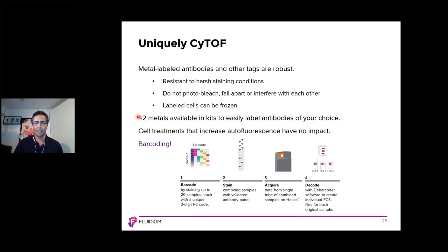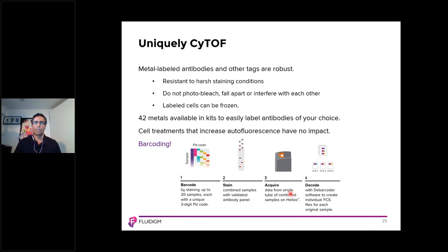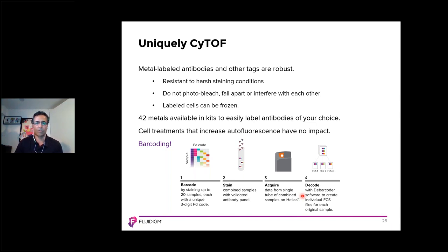Labeled cells can also be frozen and stored at minus 80°C with little to no impact on staining quality. Fluidigm also offers 42 metals available in kits to easily label antibodies of your choice. Finally, there is the barcoding option. Mass cytometry is the only high-parameter cytometry platform which enables barcoding. Fluidigm's barcoding kit allows staining of up to 20 samples, each with a unique three-digit palladium code. The barcoded samples are then combined in a single tube, processed, and acquired as a single sample. The single barcoded FCS file is then debarcoded with the CyTOF software to create individual FCS files for each original sample. Barcoding eliminates tube-to-tube variability, reduces reagent use, saves time during sample preparation and acquisition, and enables better cell discrimination.